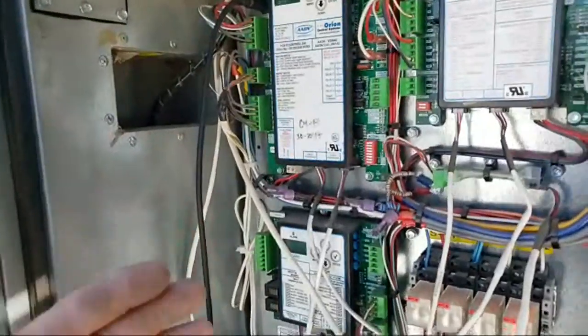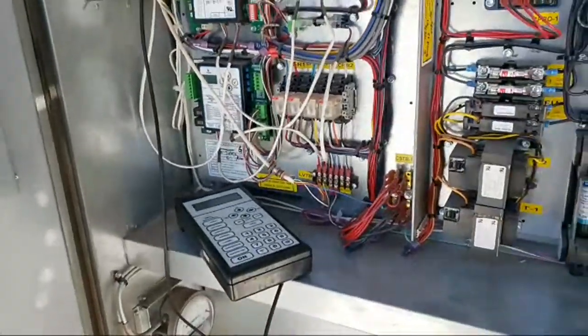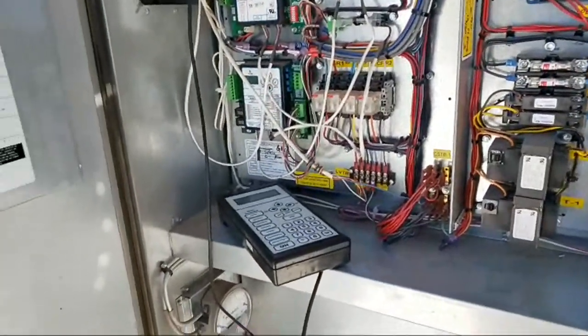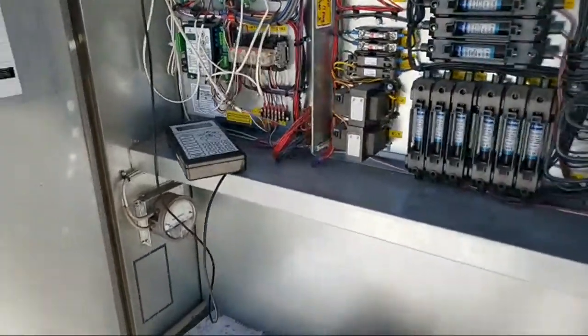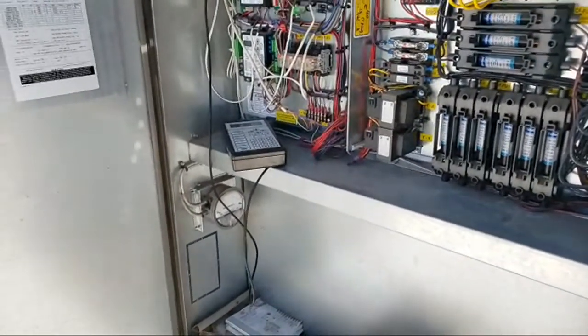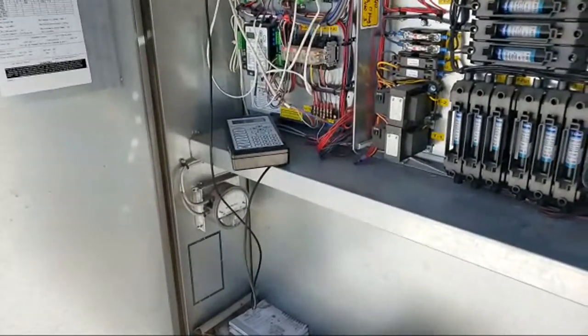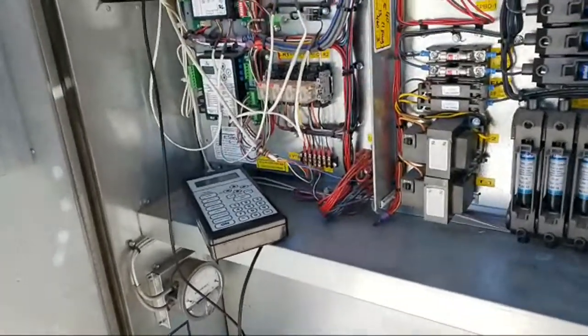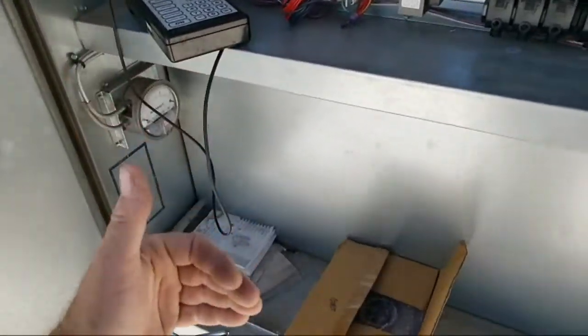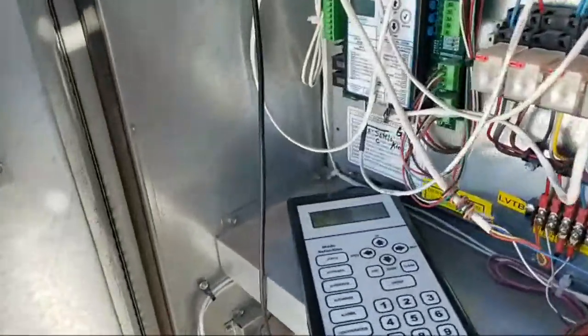That's what this thing was seeing, and it's going to keep removing moisture, keep dropping the space temperature. The relative humidity calculation goes up. It's a vicious cycle. It can't remove quite enough moisture to get the dew point down enough to get the calculated relative humidity down to stop running in that mode. Without reheating the air, you can't keep drying the air like that.